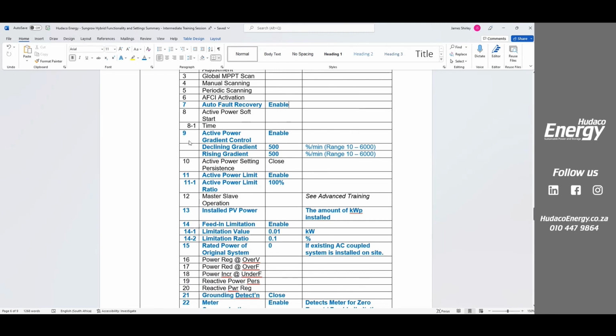Okay. The next thing is our active power gradient control. When you log in there, the standard is 10% per minute. So in other words, the rising and declining gradient of our PV production is rated at 10% per minute. So in other words, if somebody's geyser kicks in and it goes from having a 1 kilowatt load suddenly to a 4 kilowatt load, the panels will only increase at 10% per minute to cover that. So let's change that. I recommend you change that to 500 or 600. So within, let's say, half a minute, it will pick up and it'll cover that load. In the meanwhile, it'll pull that power from grid just to cover that initial spike. And you may say, well, why doesn't it just kick on immediately? The concept is the same as, you know, the guy in the Porsche or the M3.